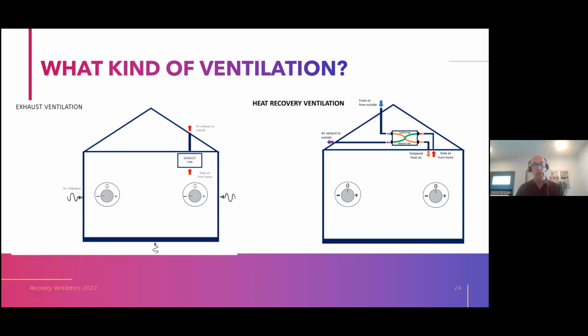Balanced ventilation, on the other hand, has equal supply CFM and exhaust CFM, so it maintains neutral pressure in the space. And you see we're showing the HRV located in the attic here, venting the stale air to the outside, bringing in fresh air from the outside, and then delivering that fresh air to the building and removing stale air from the building. And we've used that crossing paths icon there to indicate that we're exchanging the heat between those streams in that system.